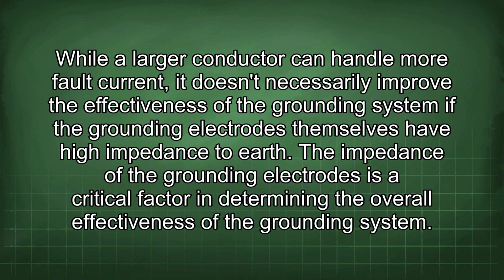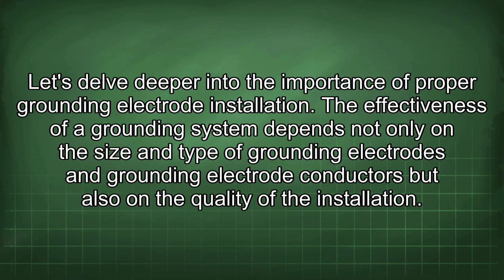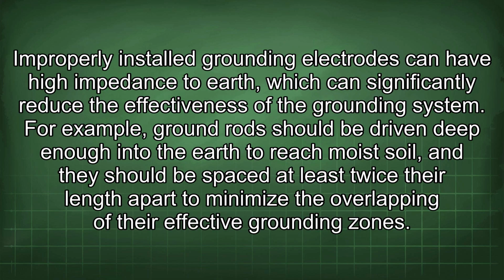The impedance of the grounding electrodes is a critical factor in determining the overall effectiveness of the grounding system. Let's delve deeper into the importance of proper grounding electrode installation. The effectiveness of a grounding system depends not only on the size and type of grounding electrodes and grounding electrode conductors, but also on the quality of the installation. Improperly installed grounding electrodes can have high impedance to earth, which can significantly reduce the effectiveness of the grounding system.